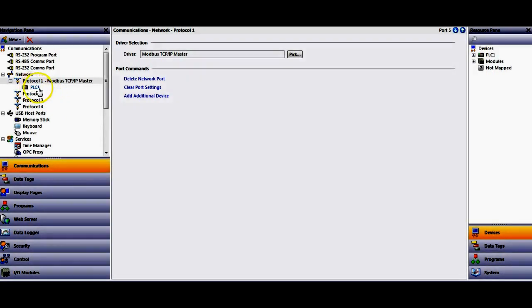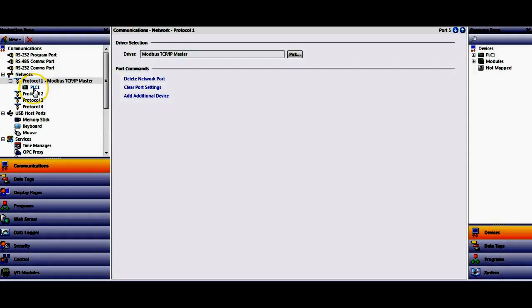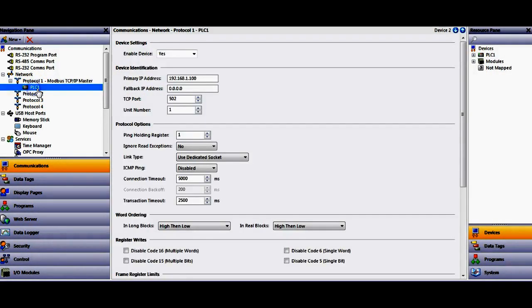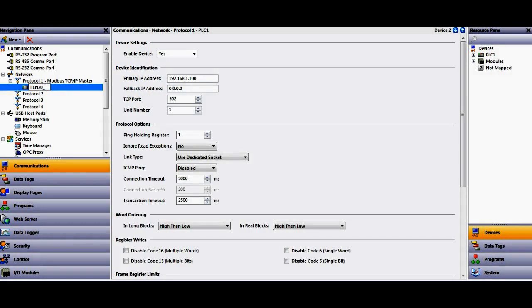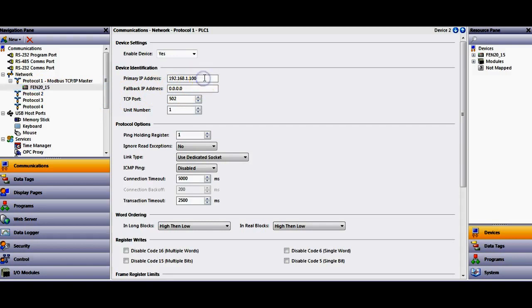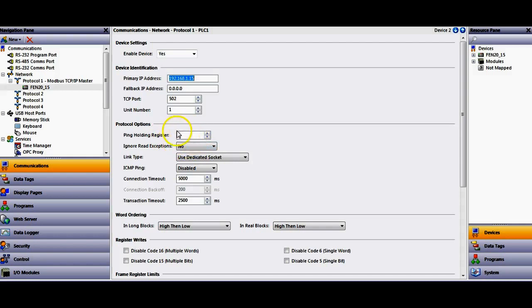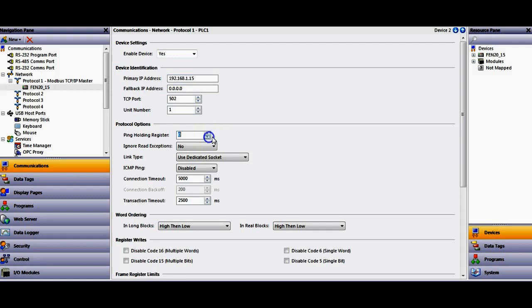And then you'll see you get one device under here, and this is going to be my FEN20 device. So if I click on this guy, I'm going to go ahead and rename this guy FEN20 underscore number 15 because that's the last octet of the IP address. So right here where it says 100, I'm going to change this to 15. And then one other very important caveat here, team, is that the ping holding register down here, this is a way that Red Lion monitors to see if the device is always connected. It's set to 400001, this is holding register one. There is no tag within the Turck device at that. So I'm going to change that to zero. That'll turn off that option.